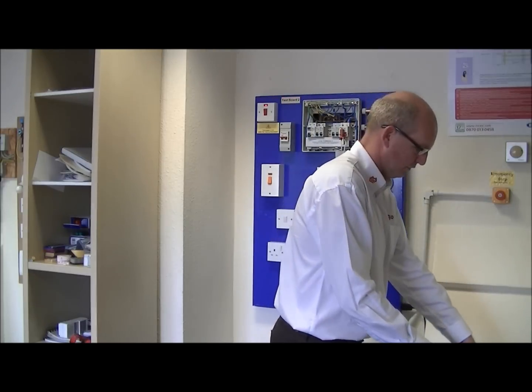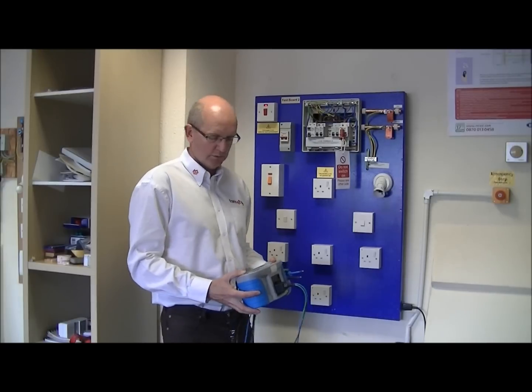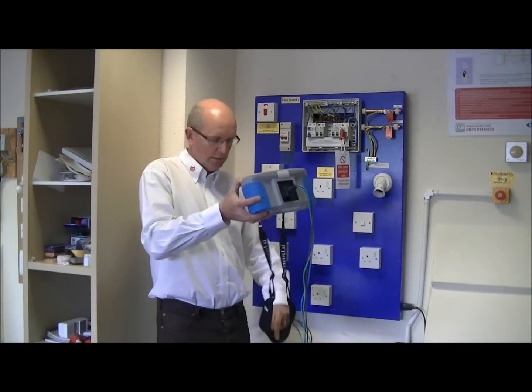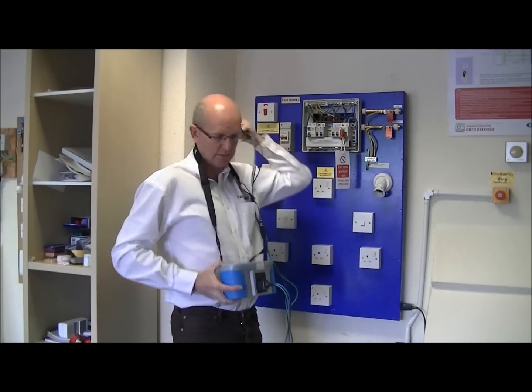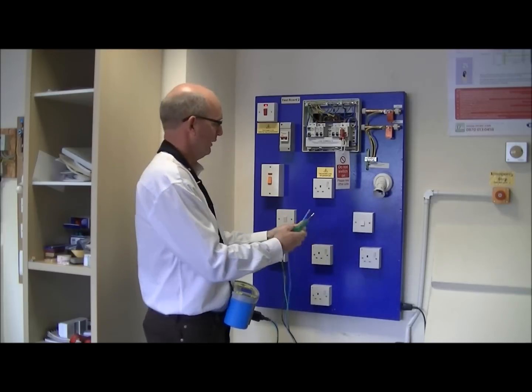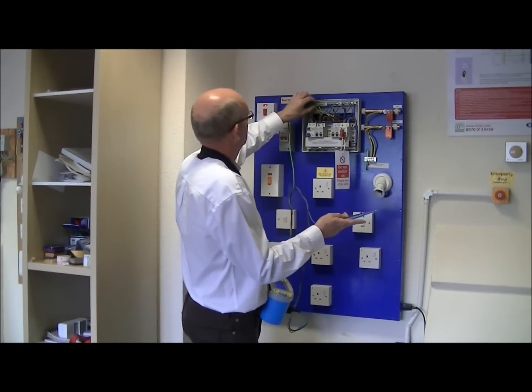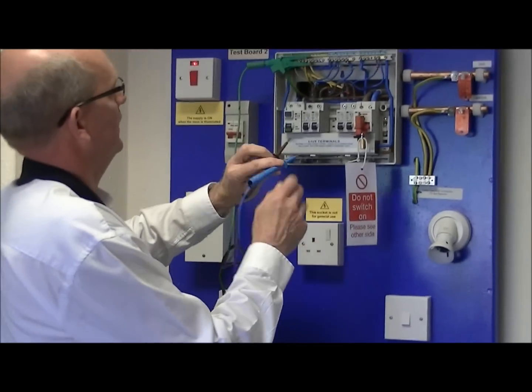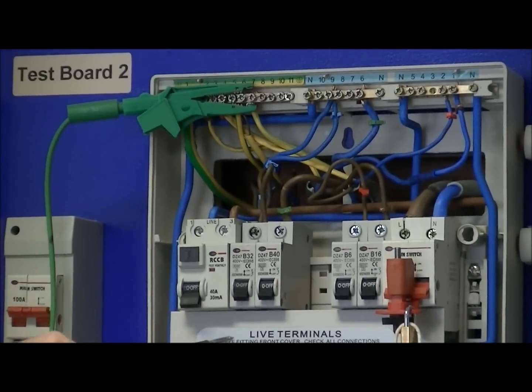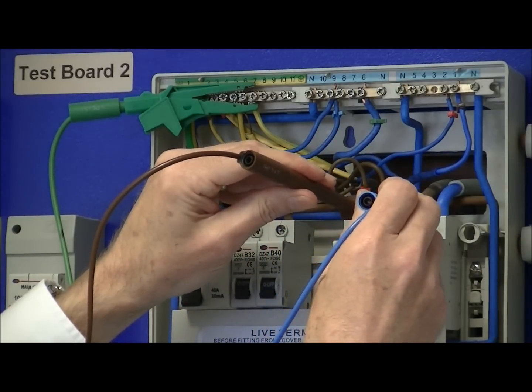We have here our multi-function tester and we're going to select our earth fault loop impedance tester to measure this prospective fault current. We require, with this particular instrument, three leads to be connected. We're going to measure this fault current at the incoming supply, so the leads are connected to the main earth terminal, or the earth bar there, and then across the incoming supplies to the main switch. When measuring these, we can't leave the installation isolated, so we select line and neutral with our probes.